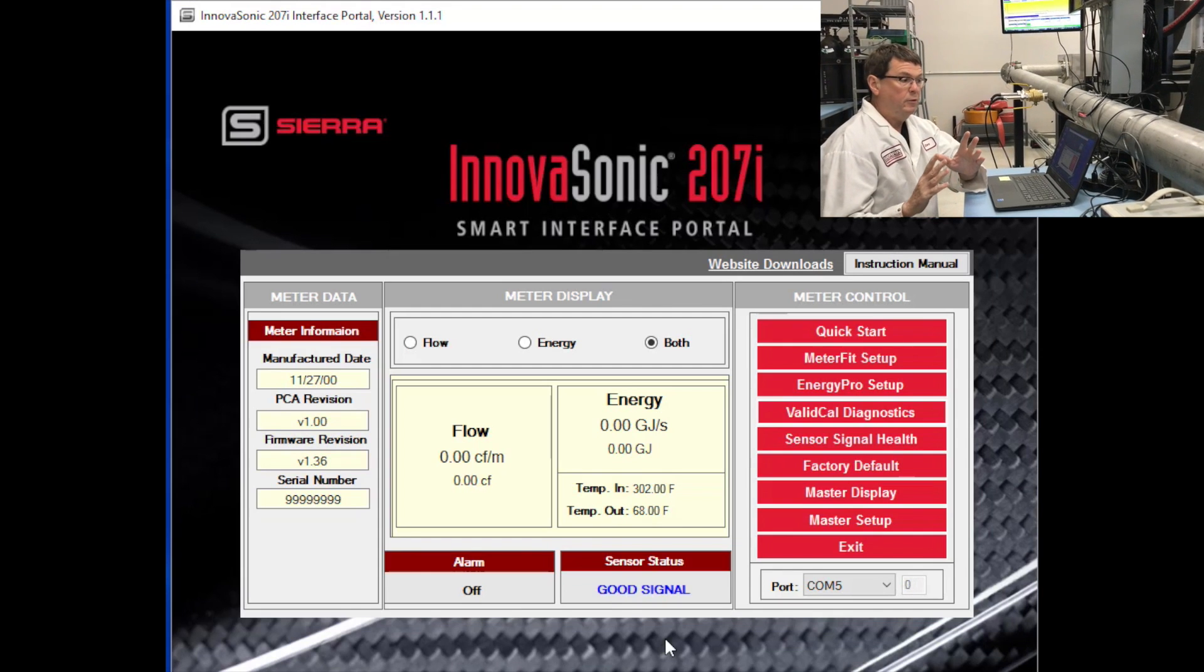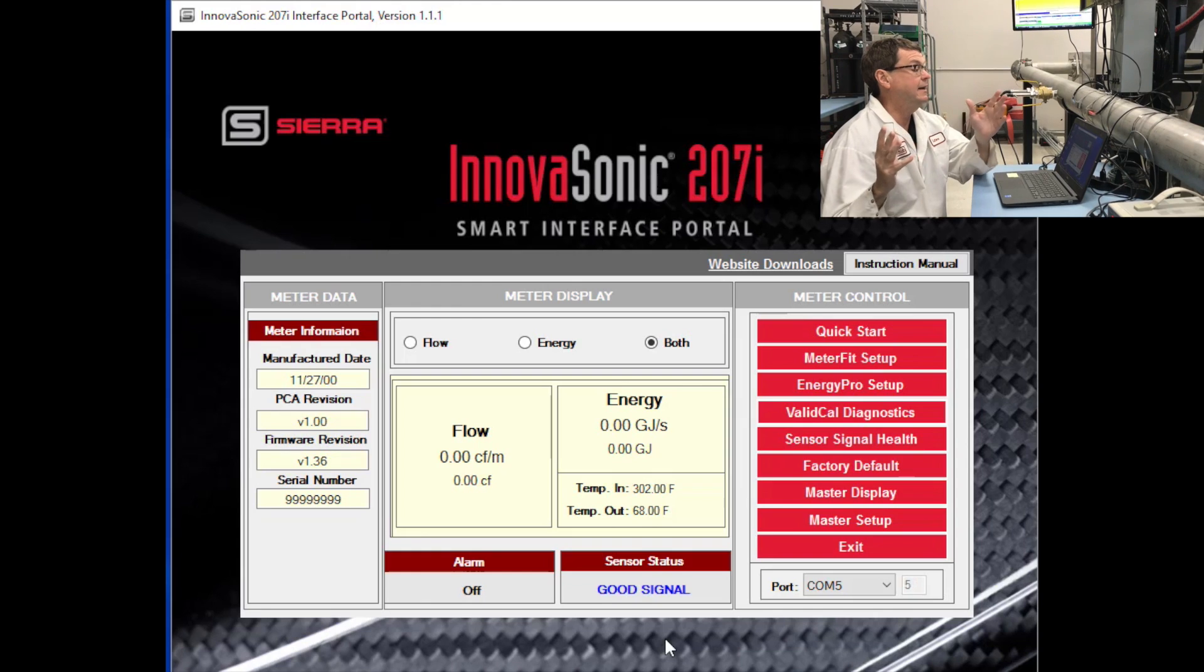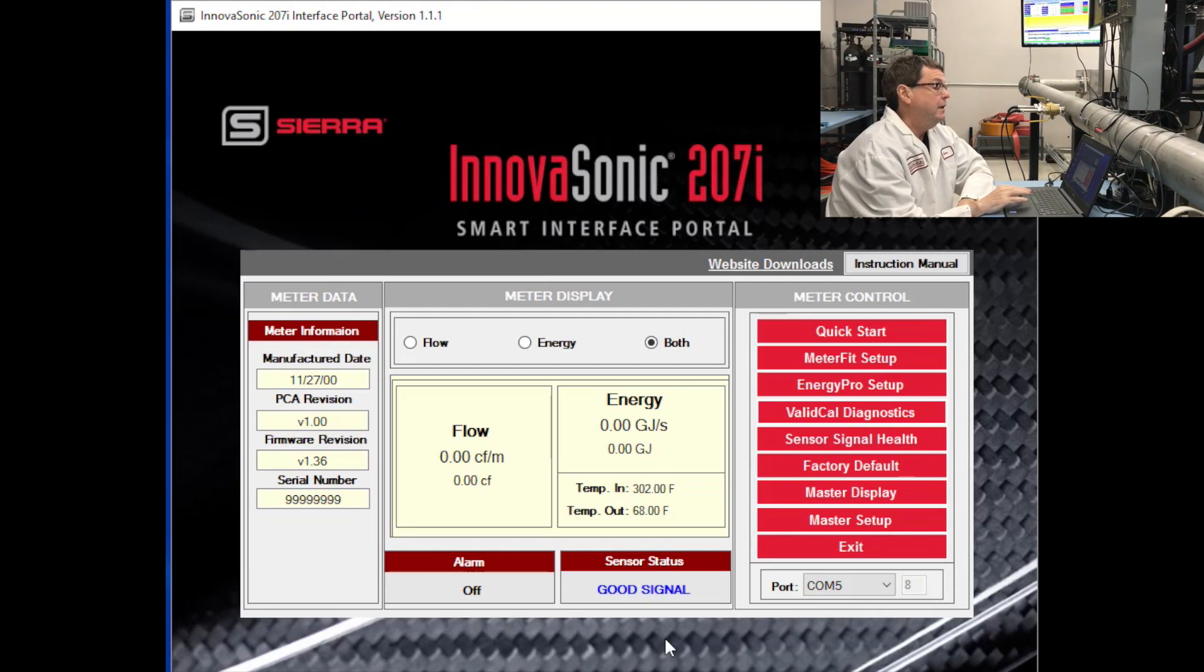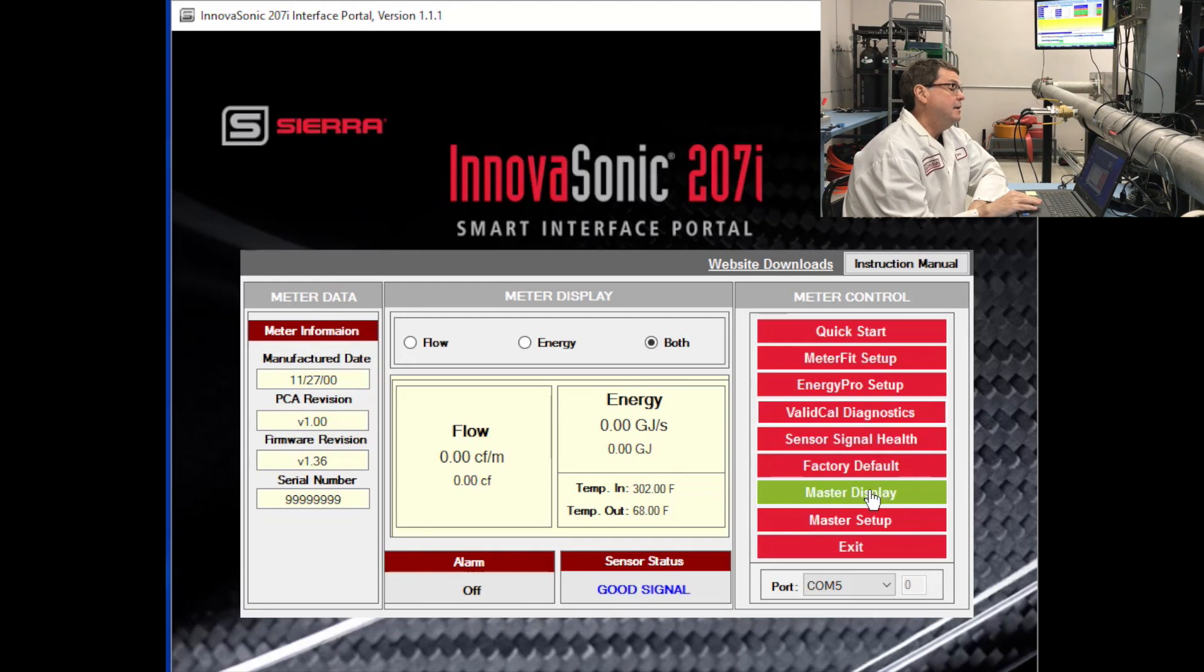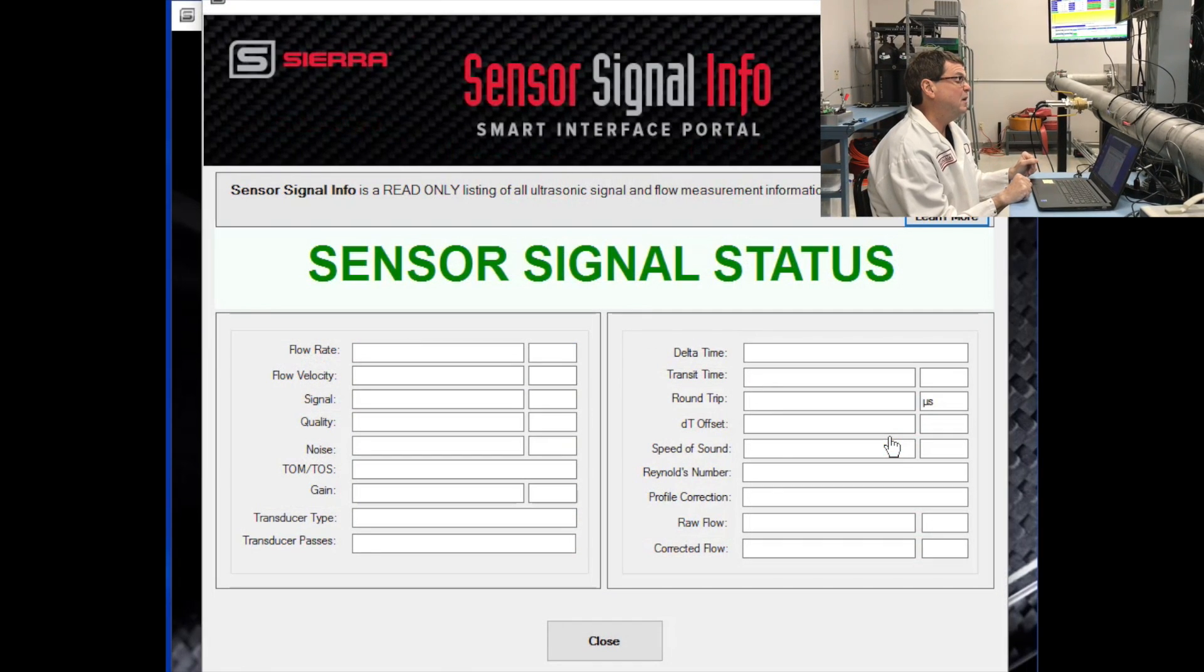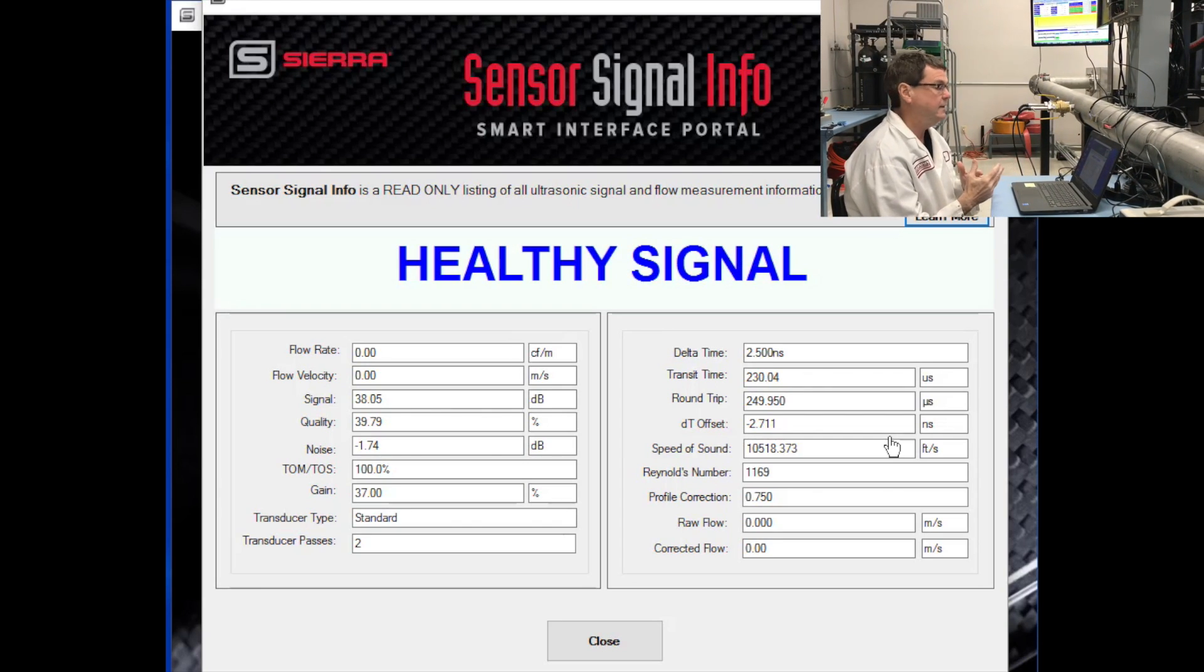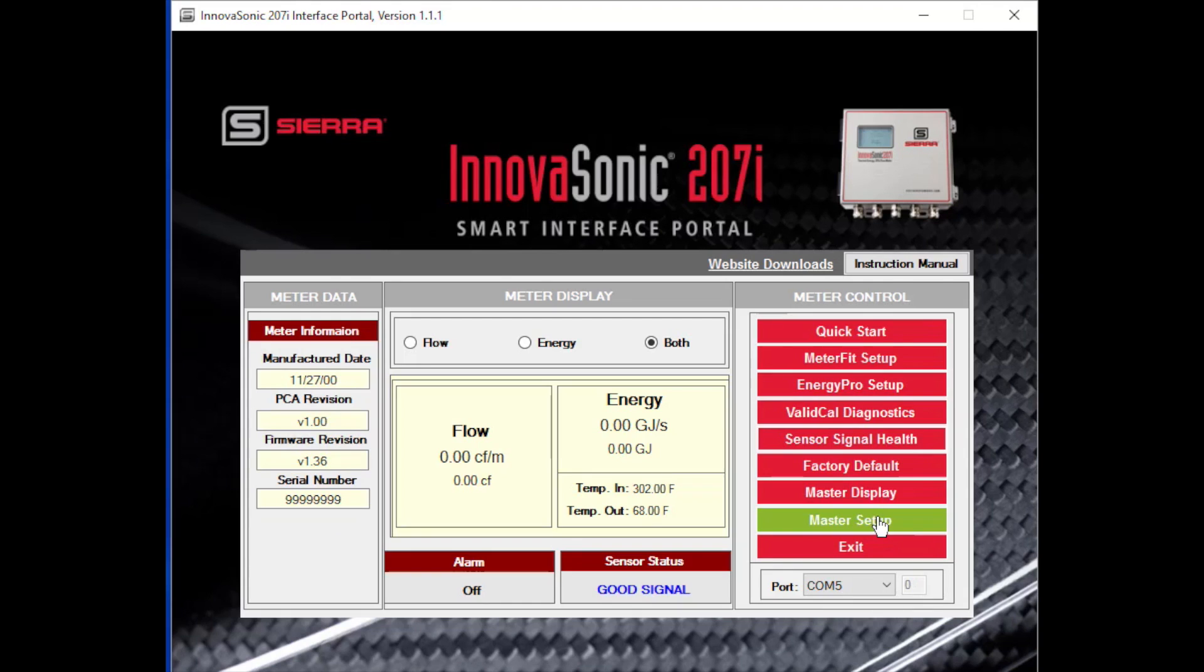Alright. So at this point, we've used the QuickStart app to set the flow portion up. We've used the EnergyPro app to set the energy measurement up. We've validated it with our ValidCal diagnostics. So we know we have a healthy meter that's measuring flow. So there are some other things that we can look at with the meter control system. There are some very good diagnostics screens. The master display screen basically gives you a summary of everything that the meter is reading. You can look at the sensor signal health, which basically tells you everything there is to know about the sensor signal itself, its gain, its quality, the signal-to-noise ratio. This is a very good screen for diagnostics if you're having difficulty getting a healthy signal.